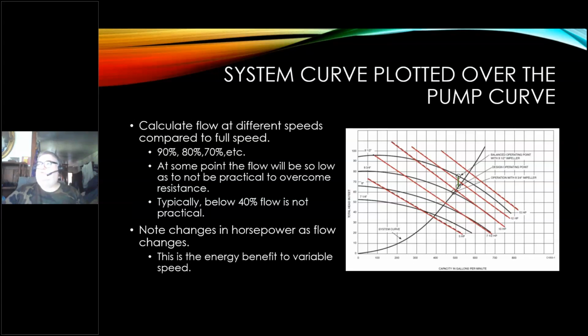90%, 80%, 70%. At some point, the flow will be so low as to not be practical to overcome the resistance. We get below that low curve. It's just turning, but we're not really sure if we're moving a lot of water. Again, you're changing the speed, you're changing the horsepower, but you're changing the flow so much that we're not really sure how well it's going to operate at that very low end. So typically, I would say that below 40% is just not practical, especially on a very large system. And I'll give you a real-world example here later on.